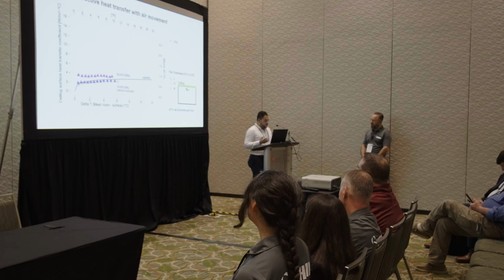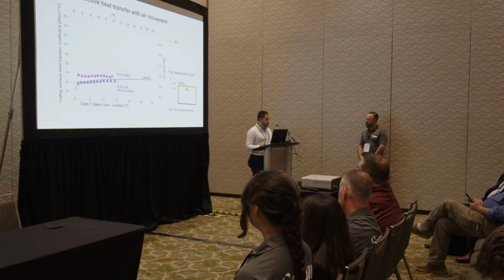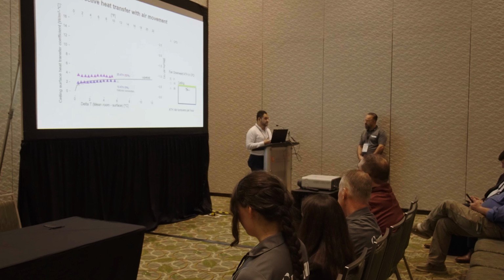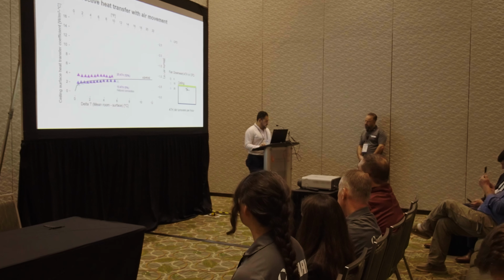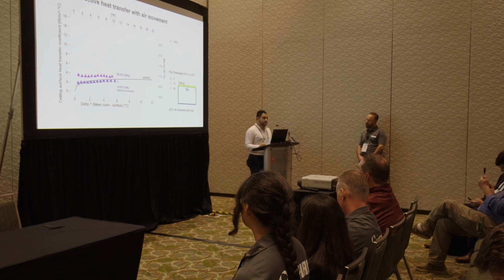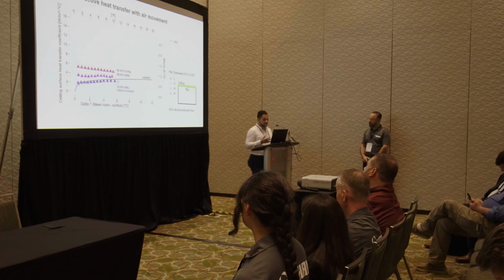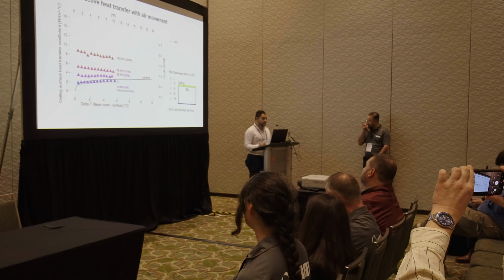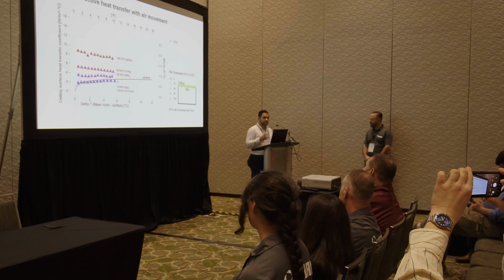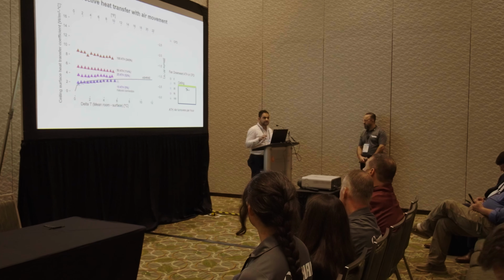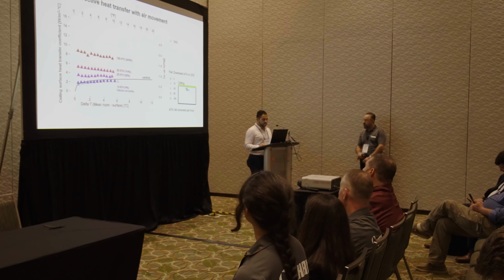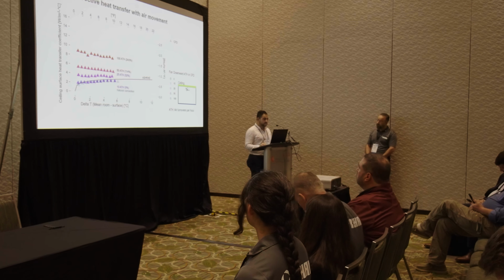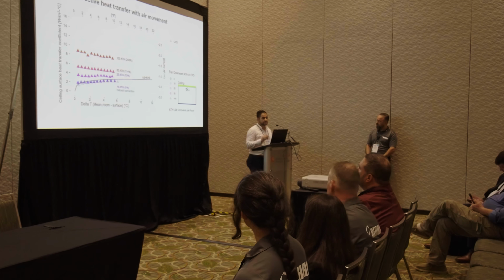It's not until the 25 ATH case that we start seeing some effects compared to the baseline natural convection case. We see about a 50% increase in the surface heat transfer coefficient, then more than 100% increase in the surface heat transfer coefficients at 50 ATH, and almost 250% increase when we're using 100 ATH. 100 ATH is at the ceiling fan's maximum speed, and 25 ATH is at the ceiling fan's minimum speed level. So you can see there's a big, drastic increase, but this is not necessarily saying that this is how much the heat transfer increases in the zone.